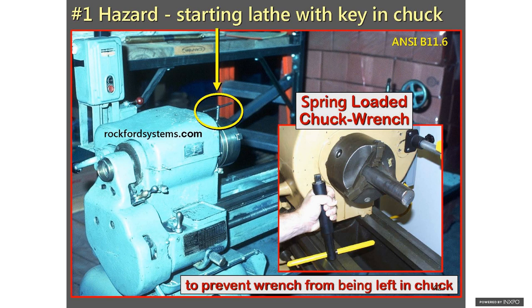Plus, in the top right corner of the photo, you see a manual motor starter, the old mechanical click to turn it on and off. The problem with those is they don't have any dropout protection. So if you lose power while that machine is running, then the power comes back 15, 20 minutes later, that lathe is going to restart unexpectedly. That's why you want to replace a manual motor starter with a magnetic motor starter to provide dropout protection, also known as anti-restart.